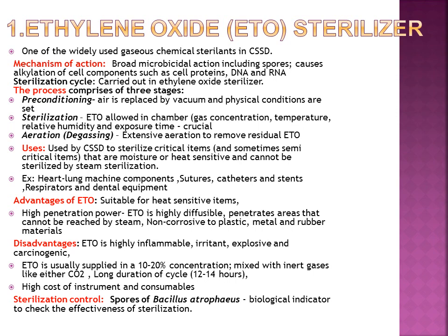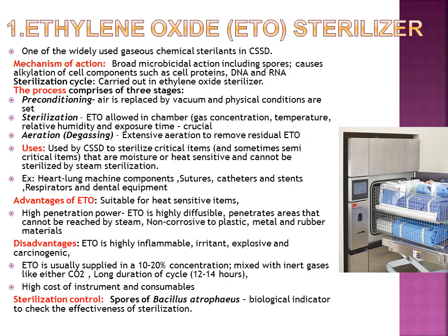Preconditioning, air is replaced by the vacuum. Sterilization, ETO is allowed in the chamber. So gas concentration, temperature, humidity, exposure time should be noted. Then aeration, that is degassing. So extensive aeration to remove residual ETO, because ETO is toxic and carcinogenic.